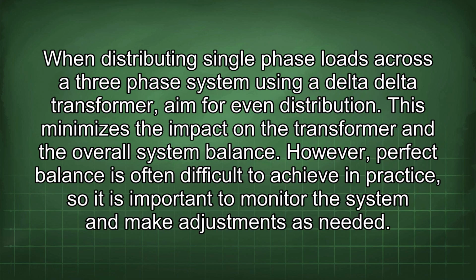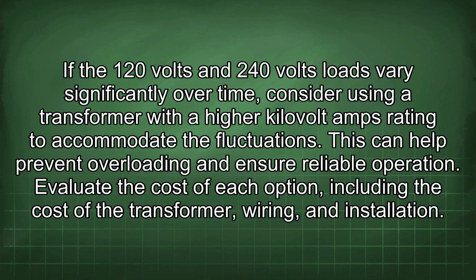When distributing single-phase loads across a three-phase system using a delta-delta transformer, aim for even distribution. This minimizes the impact on the transformer and the overall system balance. However, perfect balance is often difficult to achieve in practice, so it is important to monitor the system and make adjustments as needed. If the 120 volts and 240 volts loads vary significantly over time, consider using a transformer with a high kilovolt amps rating to accommodate the fluctuations. This can help prevent overloading and ensure reliable operation.